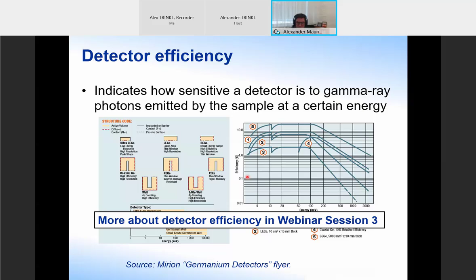The way this kind of detector works is quite a comprehensive process. In order for it to work properly without a lot of noise, we need to cool our detector down to cryogenic temperatures, less than, let's say, minus 170-something degrees centigrade. That's what they need to function properly. Traditionally, this was always done using liquid nitrogen, which has a boiling point of around minus 196 degrees Celsius. Liquid nitrogen was chosen because it matched up rather well with the ideal temperature for a germanium detector. Nowadays, you'll see more and more different kinds of electrical cooling mechanisms where you don't have to refill your liquid nitrogen every so often. You just keep it plugged in over time, and eventually maybe you have to change out some mechanical parts, though a lot of development is happening in that field as well.